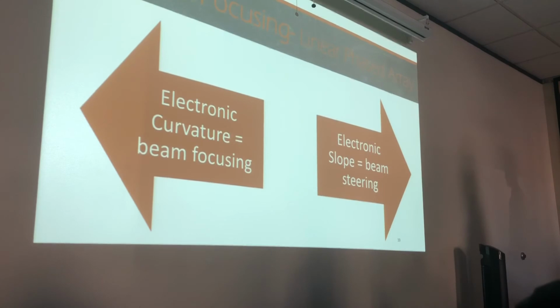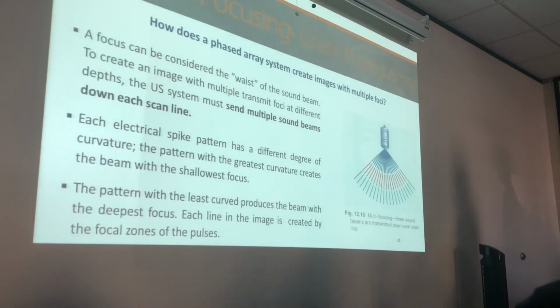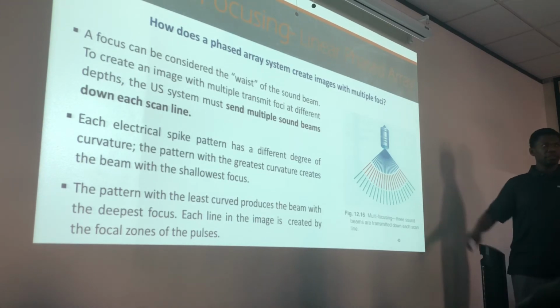So again, guys, electronic curvature, beam focusing. Okay, electronic slope, beam steering. Okay. I think I got two things. Transmit, still on transmit focus, we're talking about multiple focus, then I have dynamic receive focus. Then we're done. Alright? So, how does a phased array system create images with multiple focuses? Simple, guys. It's going to send multiple sound beams down each scan line. However many focuses you have. So apparently, just looking at this one, 3 focuses, right?